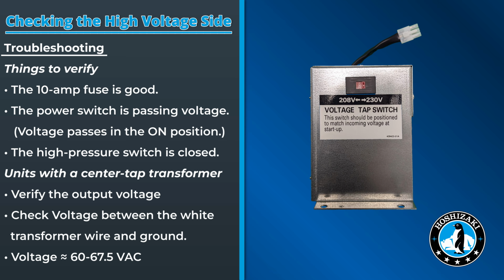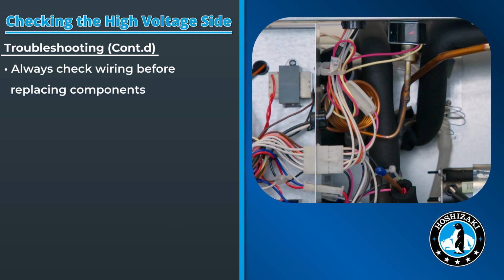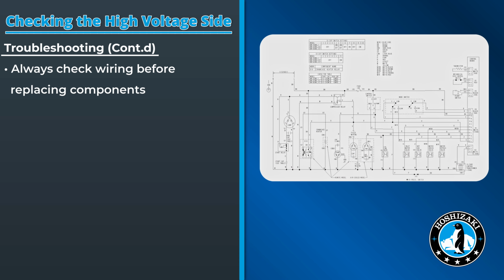On units equipped with the center tap transformer, you will also need to verify the tap output voltage. To test this, measure the voltage between the white transformer wire and ground. A properly functioning transformer should read approximately 60 to 67.5 volts. Before replacing any components, always inspect your wiring between each component to confirm that the wires are connected properly and the voltage is being passed through. To identify wire routing and component location, refer to your wiring diagram found in the unit's service manual.